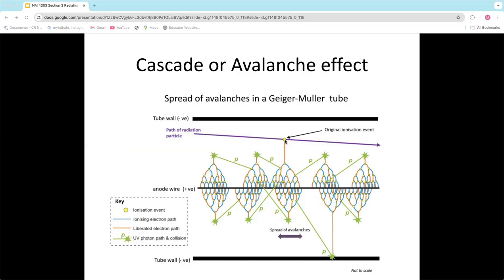However, remember I said that the voltage is really, really high in the GM. So we've got our voltage really strong. As soon as this reaction happens, the electron and the ion pair are pulled towards the anode and the cathode with such great force that along the way they strike other argon gas molecules and cause more ionization reactions. That's what this represents here: we had our original ionization event, and then as it travels, it makes more and more reactions.